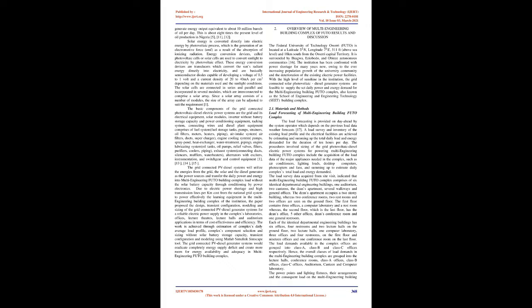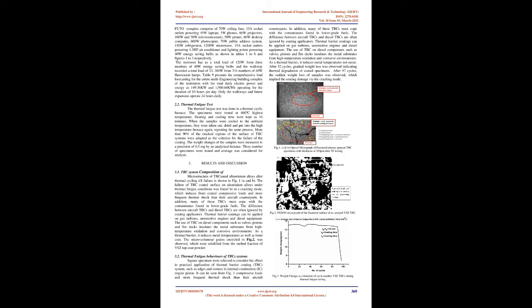The basic components of the grid-connected photovoltaic diesel electric power systems are the grid and its electrical equipment, solar modules, inverter without battery storage capacity and power conditioning equipment, racking system, connecting wires, and diesel plant equipment. The diesel plant comprises the fuel system, fuel storage tanks, pumps, strainers, oil filters, meters, heaters, piping, air intake system, air filters, ducts, supercharger, engine cooling system, pumps, spray pond, heat exchanger, water treatment, piping, engine lubricating system, oil tanks, oil pumps, relief valves, filters, purifiers, coolers, piping, exhaust system, connecting ducts, silencers, mufflers, water heaters, alternators with exciters, instrumentation, and switchgear and control equipment.